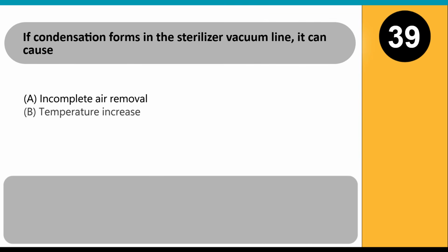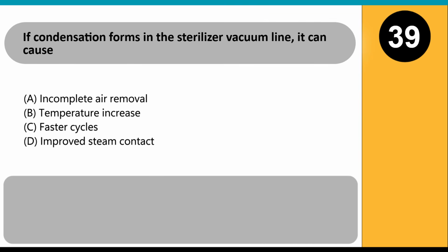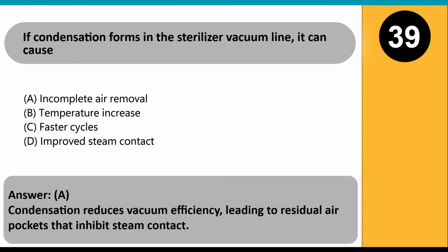If condensation forms in the sterilizer vacuum line, it can cause: A. Incomplete air removal. B. Temperature increase. C. Faster cycles. D. Improved steam contact. Answer A. Condensation reduces vacuum efficiency, leading to residual air pockets that inhibit steam contact.